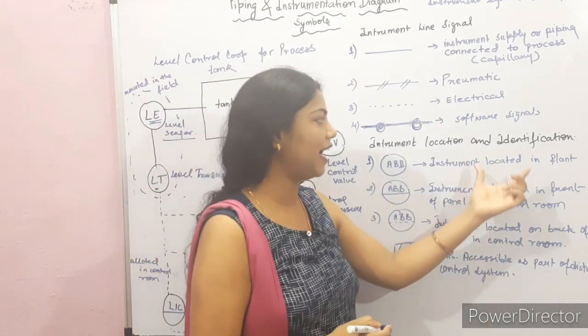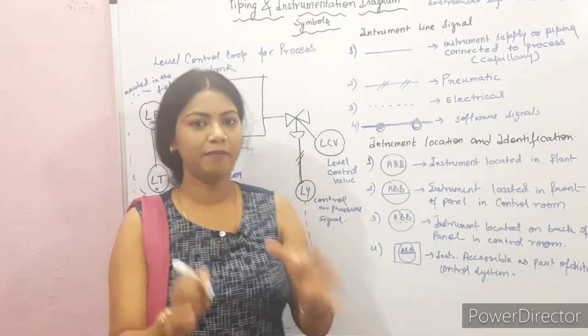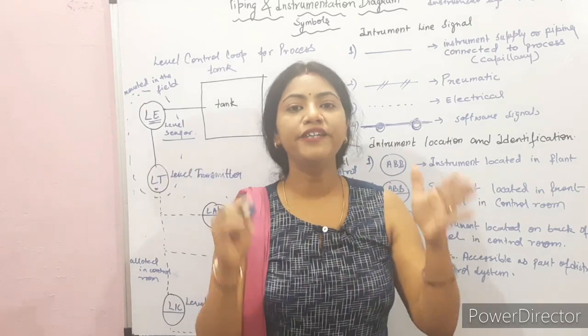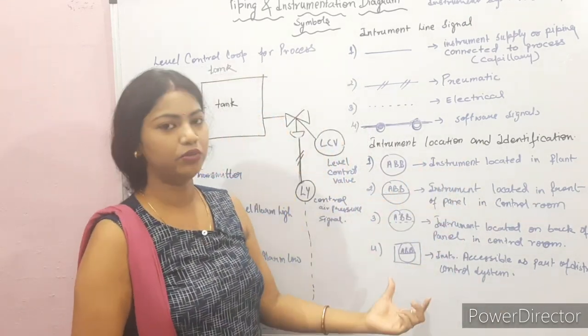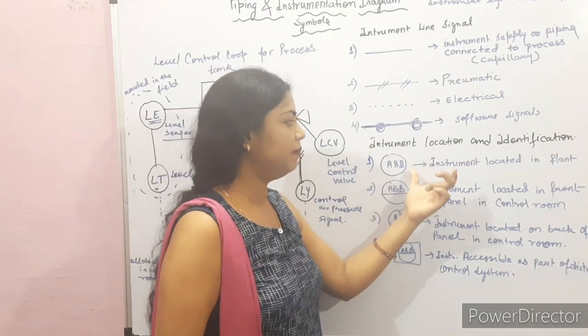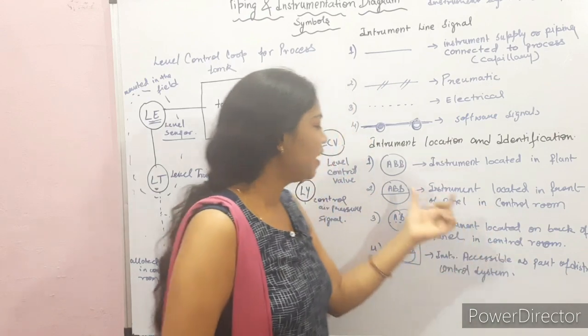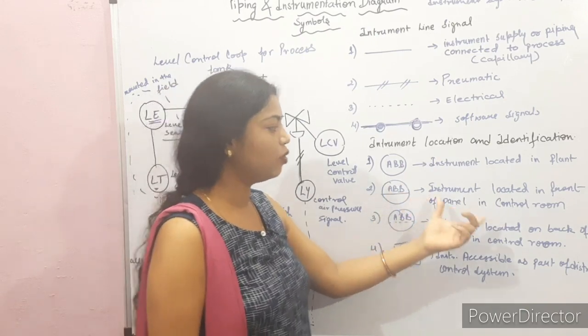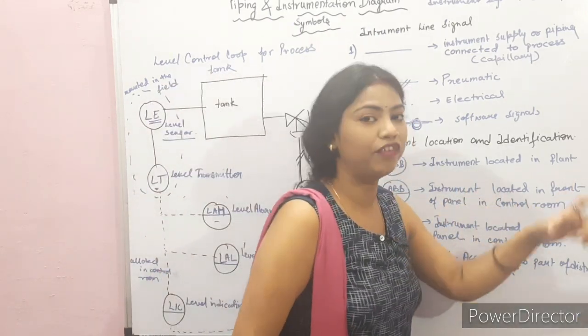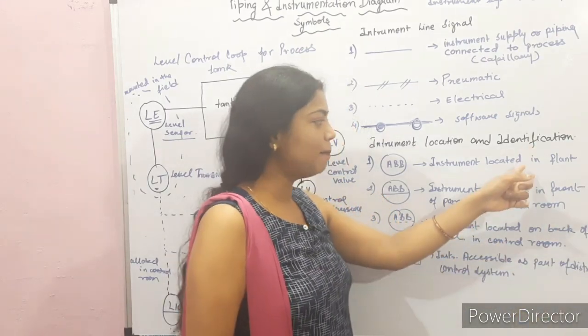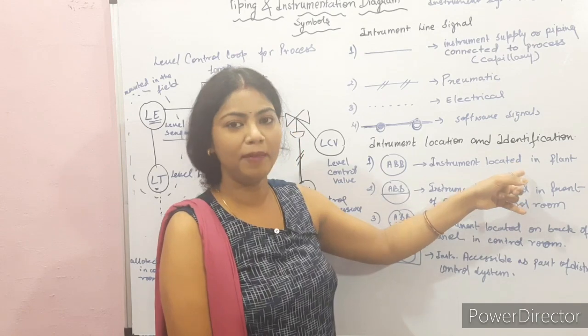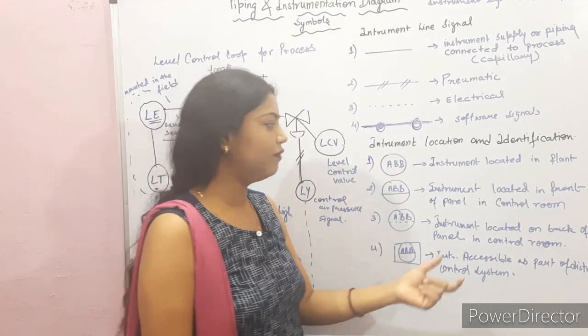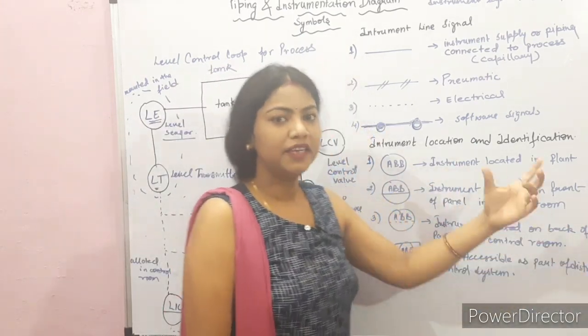Now let's talk about instrument location and identification. To represent where an instrument is located, we use specific symbols. A round shape — a circle with letters — represents an instrument located in the plant. If there is a horizontal line inside the circle, it represents an instrument located in front of the panel in the control room.